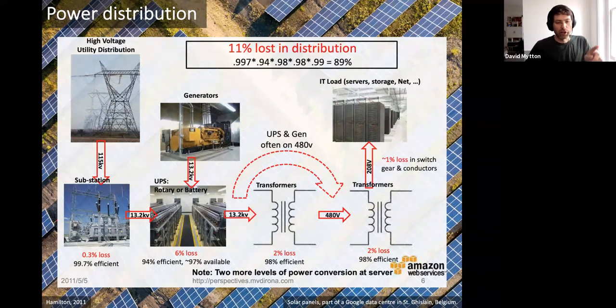There are losses at each stage, even as it gets to the IT load - about 11% power loss, which you can relate to that 1.10 PUE from Google. They're very efficient and managed to reduce those losses, but there are still losses just in operating a facility doing nothing, because of power distribution.